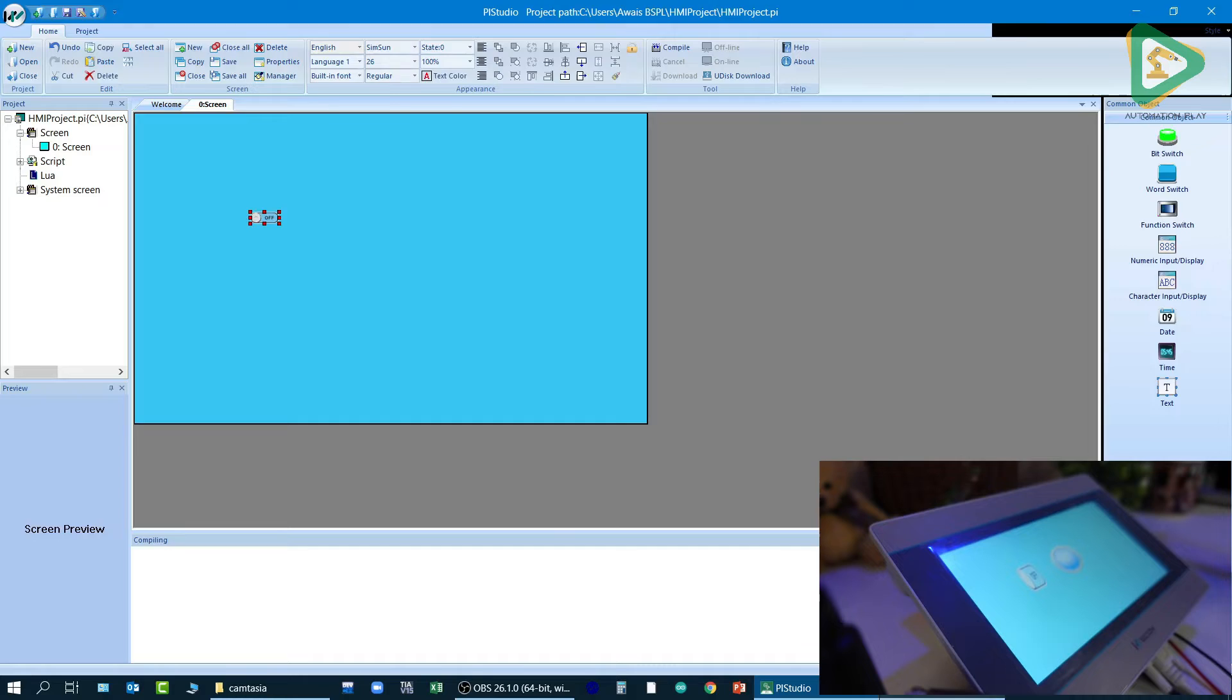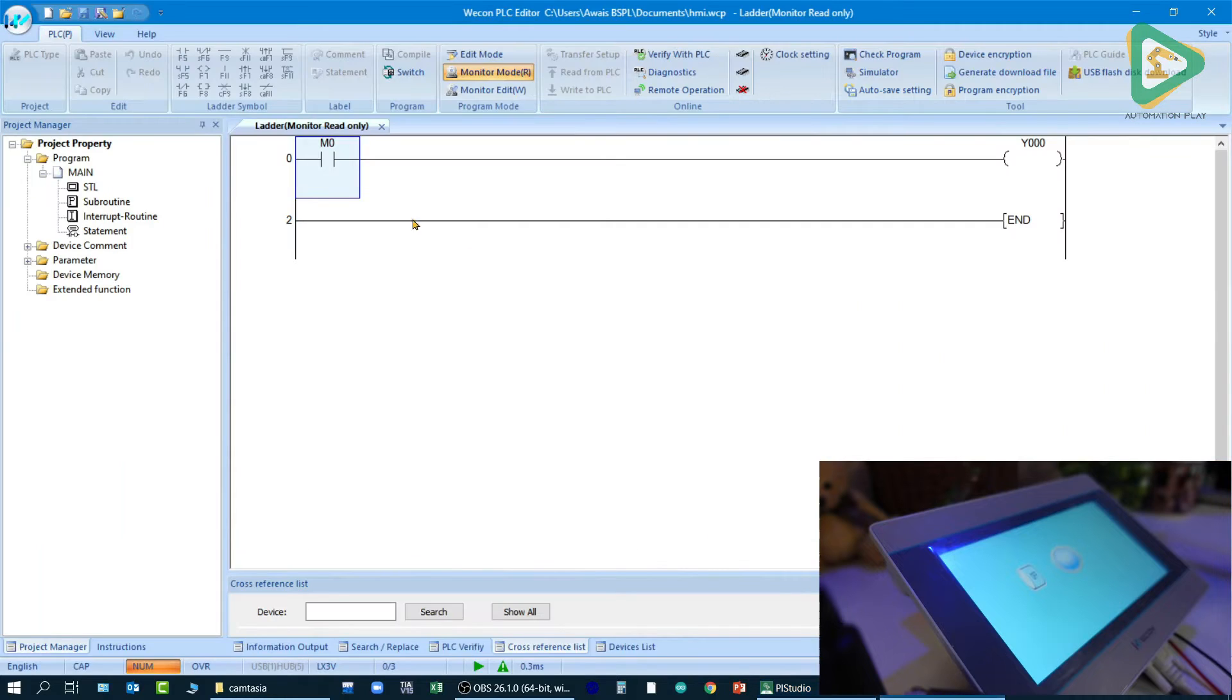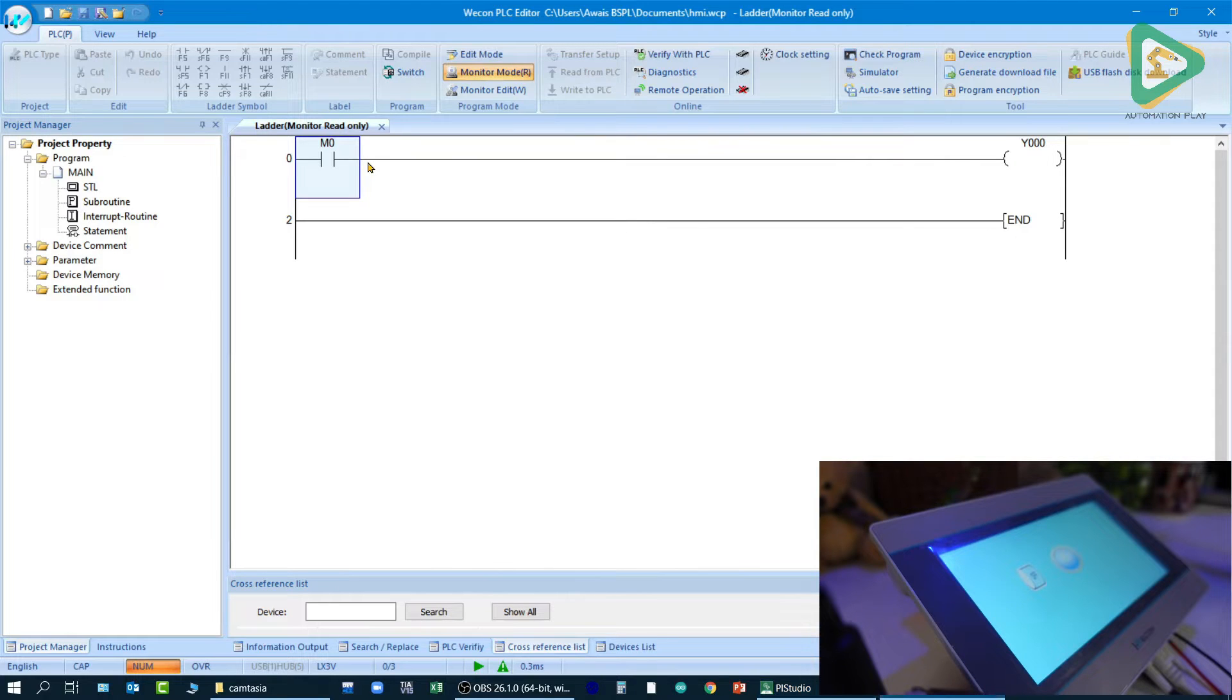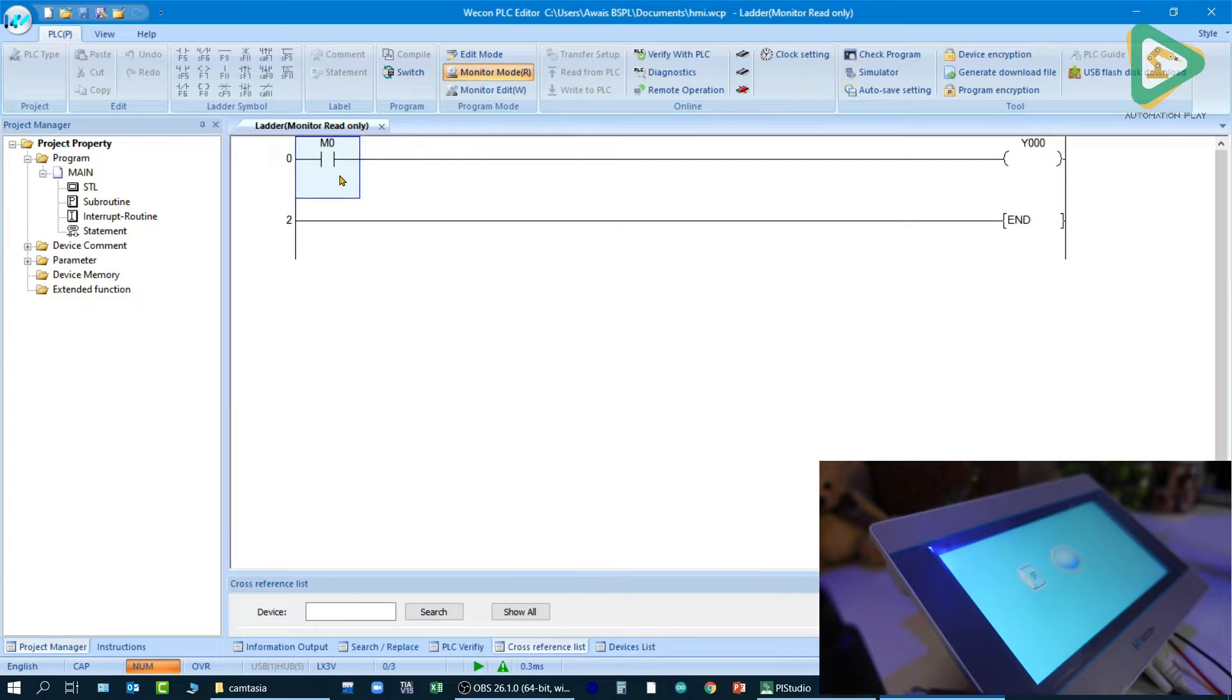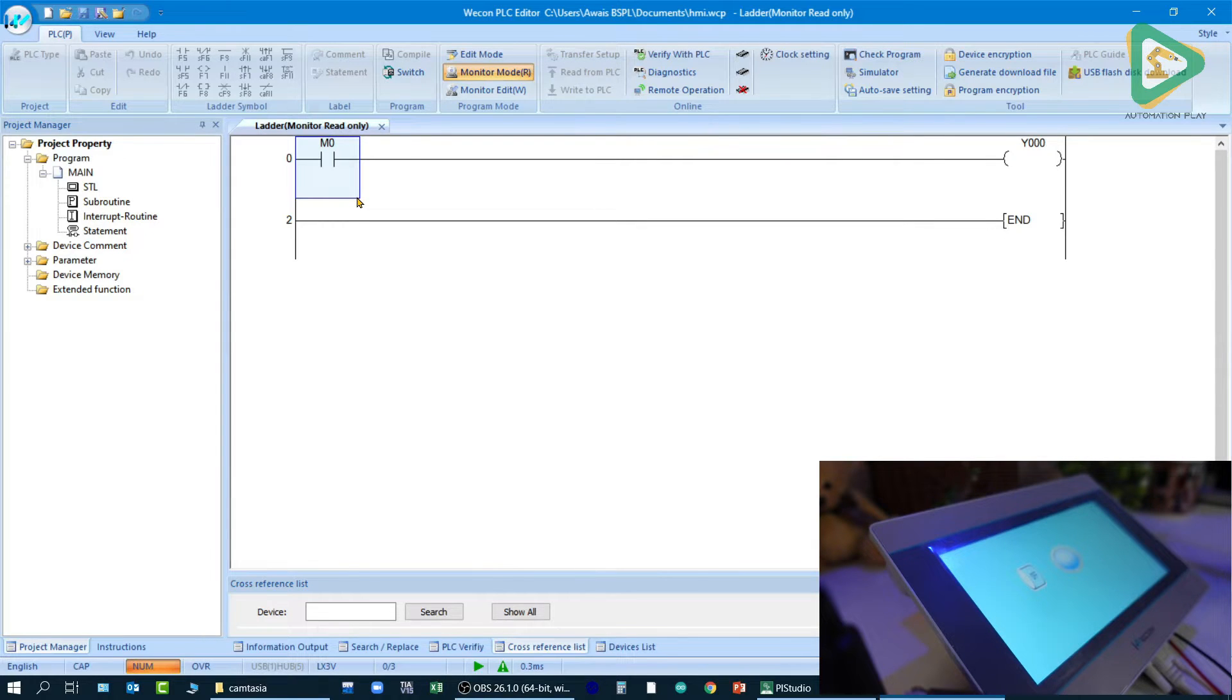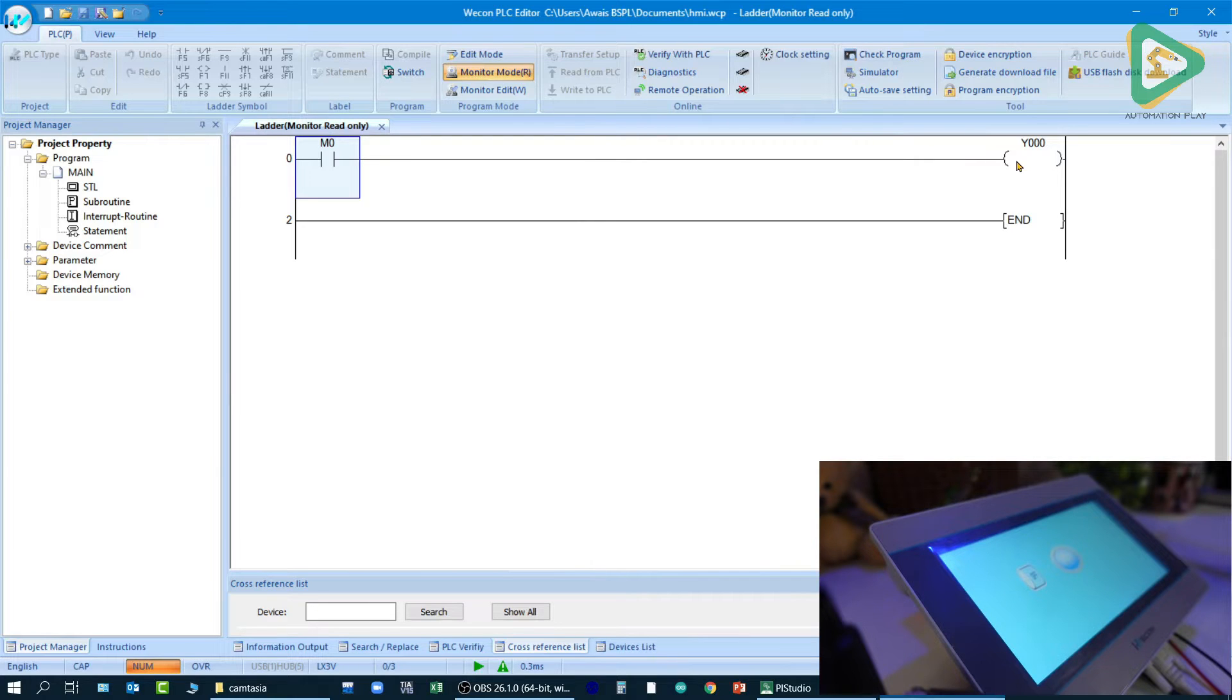Now the PLC program that I've created is a simple M0 bit, which are used for memory buttons on HMI or latching switches as well. So X0 won't work because that is a physical bit used for physical devices. So M bits, memory addresses, are used for buttons in HMI, and Y0 is a physical bit which can be used as a read function to display an indication that is being shown over here.